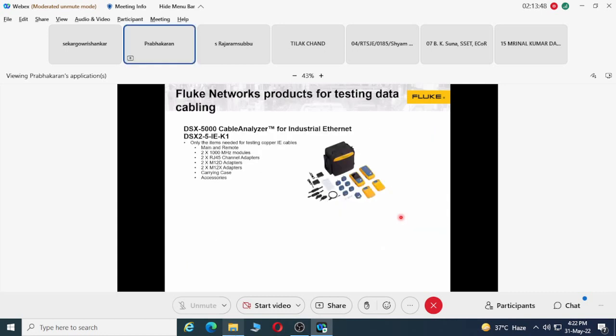What we offer here is actually coming from Fluke Networks - a product called DSX 5000 cable analyzer, which is an industrial Ethernet cable tester, or cable analyzer. You can test all kinds of cables used for industrial Ethernet or Ethernet communication, and it can also have an optional fiber optic module. That means you will be able to do both fiber optic as well as Ethernet or copper cable communication systems testing using these two testers.